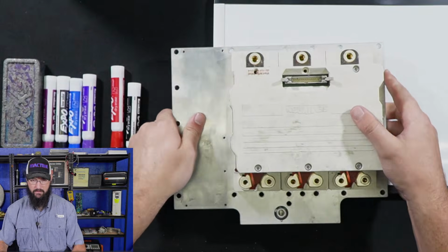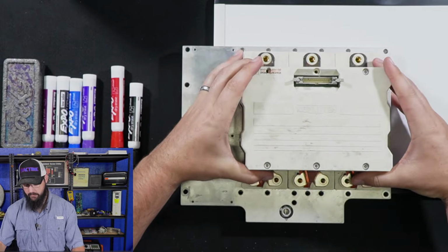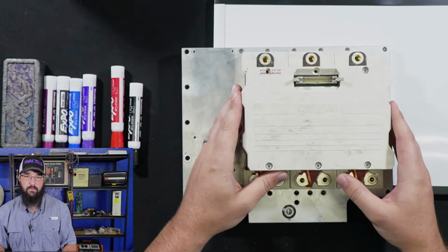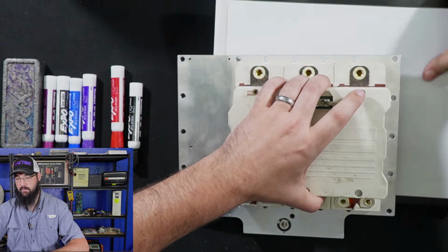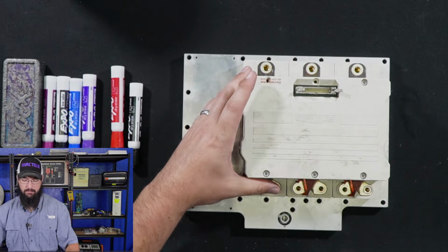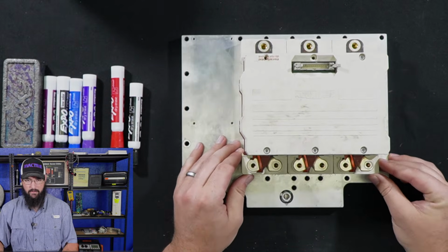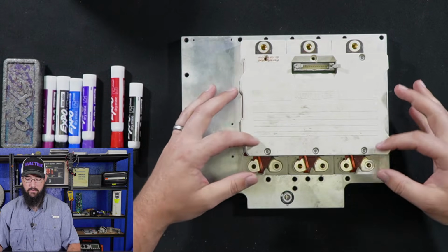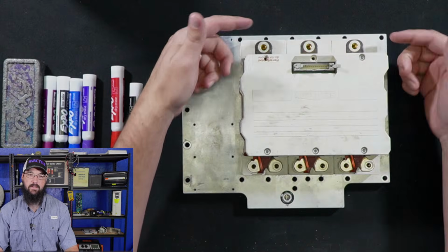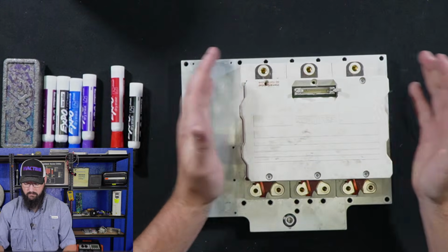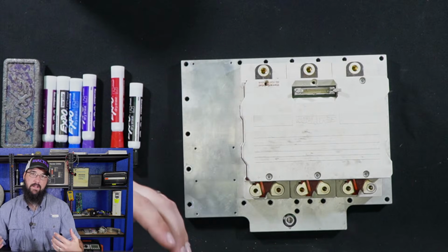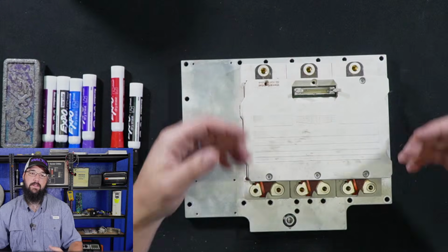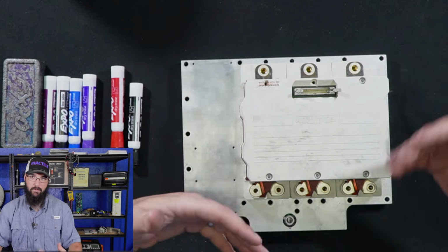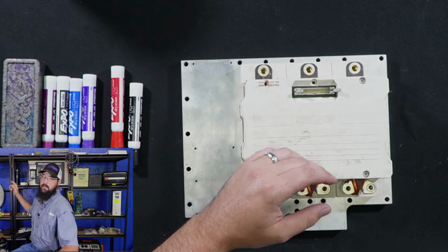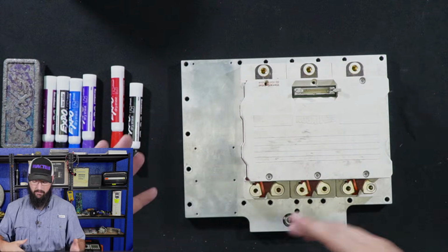So let's get this set up. This is an IGBT module. Danfoss refers to this in the Turbocor compressor as an inverter, and that's completely accurate, because we have DC power coming in here. It goes through a set of transistors we call an IGBT, and we have AC coming out the other side. In that process, we're taking DC and converting it back into AC, hence an inverter, versus a rectifier, with an SCR right here, rectifying from AC back into DC, yada yada yada.